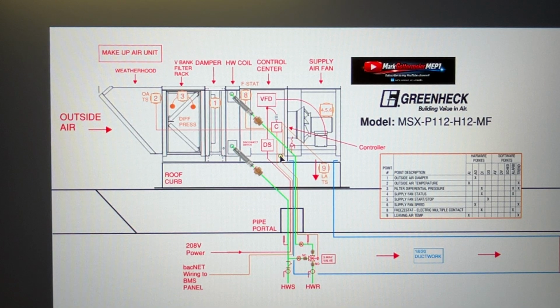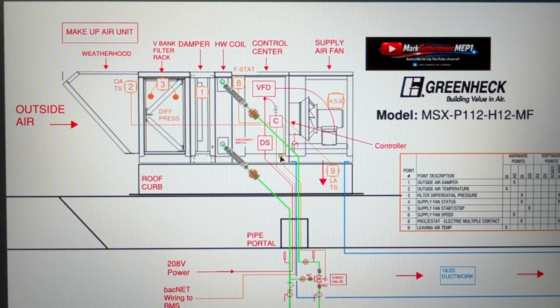In this one, this is a fire hall project, and this makeup air unit serves the apparatus bay where the truck engines are. So in the wintertime, when the garage bay doors are open, this unit will serve as a heat source for that space while the garage doors are open, so that you don't lose all of the heat when they're open. So this won't run all the time, but you certainly need a heating element to treat that outside air, in the wintertime, to warm it up before it hits the space.